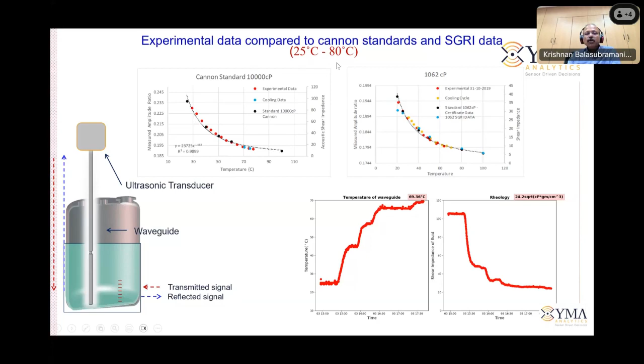In order to do that, we had to make sure that our sensor matches with some of the calibration fluids that you see here. So these are all the calibration fluid data, the dots, and the line is measured by our curve. There's a phenomenal matching between the standard data and what we are doing. This particular one is limiting from 25 degrees Celsius to 80 degrees Celsius.